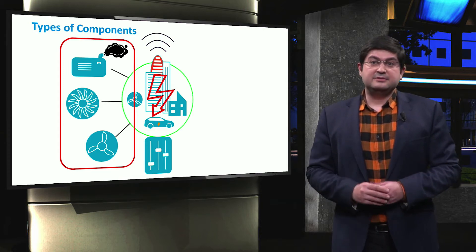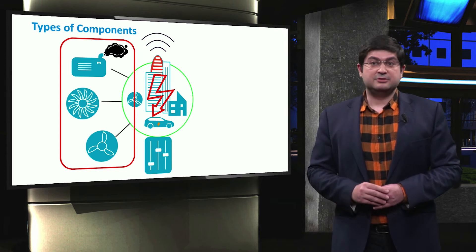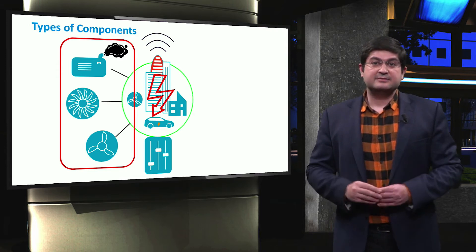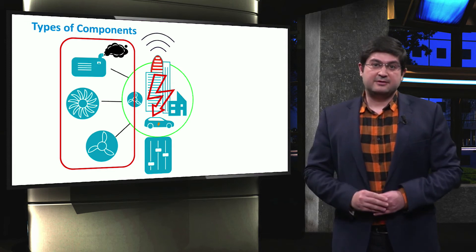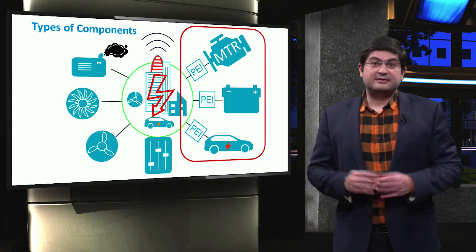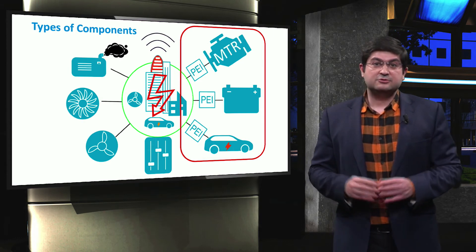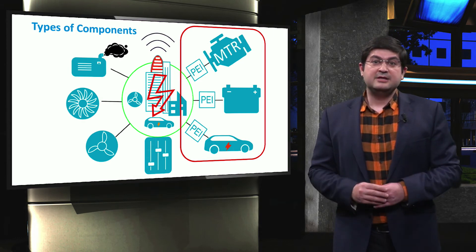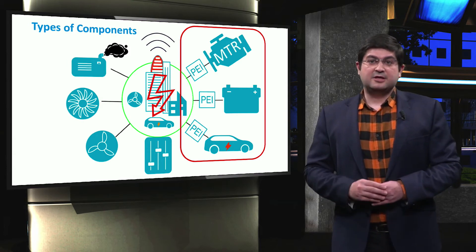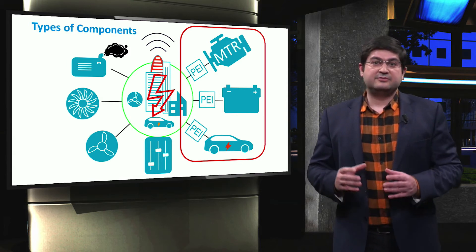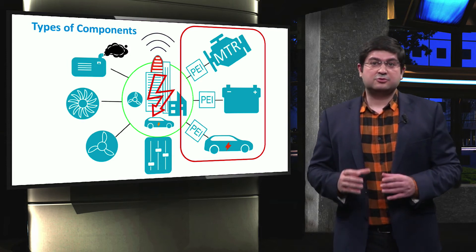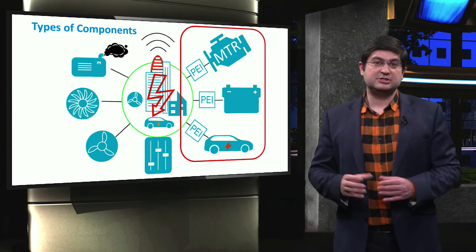On the one hand, due to their direct connection to the microgrid, these types of distributed generators will inject a large amount of short-circuit current. On the other hand, there are other types of electrical components which are connected to the microgrid through power electronic interfaces. These units typically inject a lower amount of short-circuit current due to the presence of highly controlled power electronic switches.